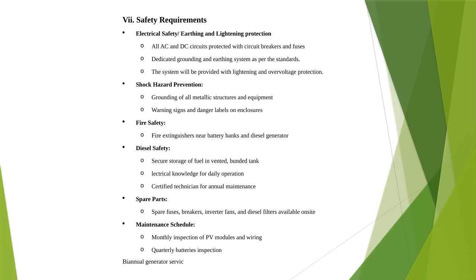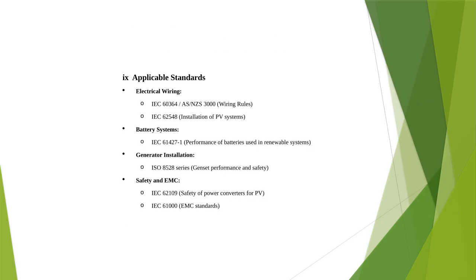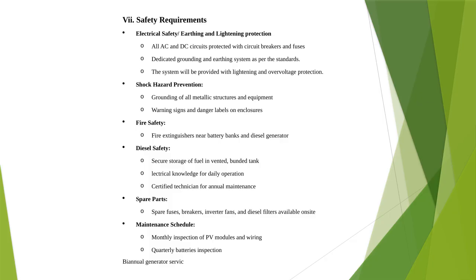So, maintenance requirements. For our system to be maintained properly, we would need a skilled technician. The technician who will be maintaining the system should have basic electronic knowledge for daily operation. He should be a certified technician for annual maintenance. The spare parts will be stored on site for eventual maintenance. We'll have some spare fuses, some spare breakers, some inverter fans, and diesel filters available on site.